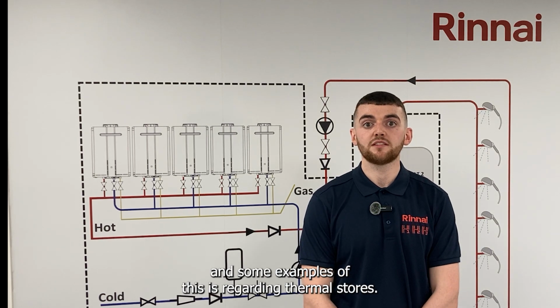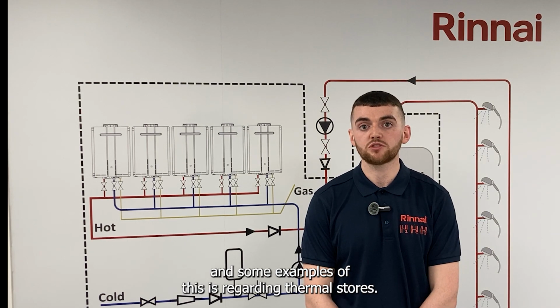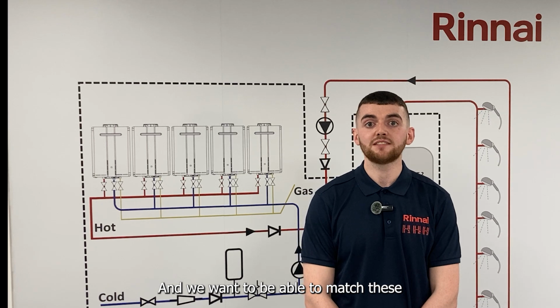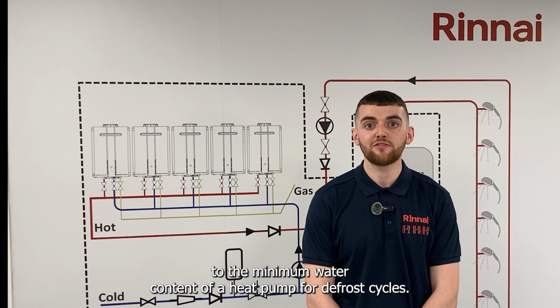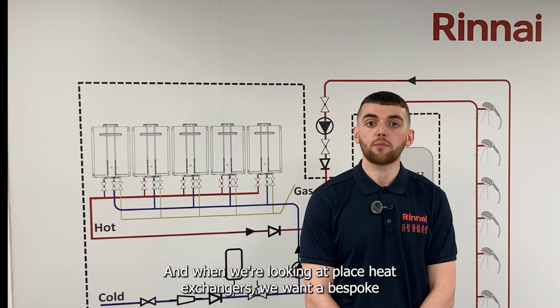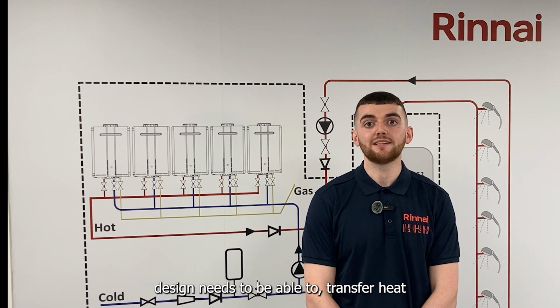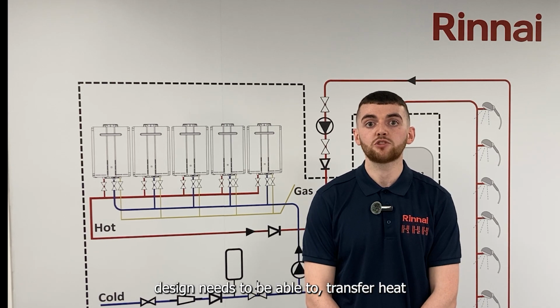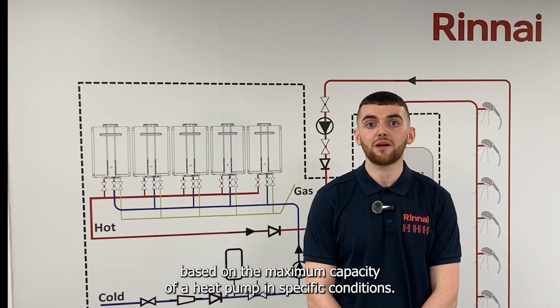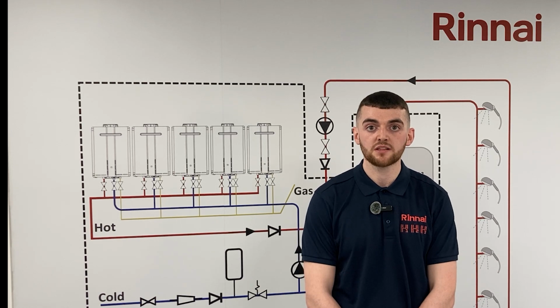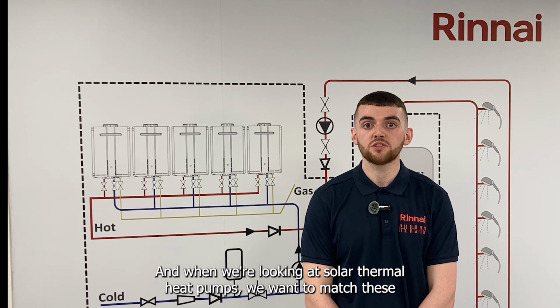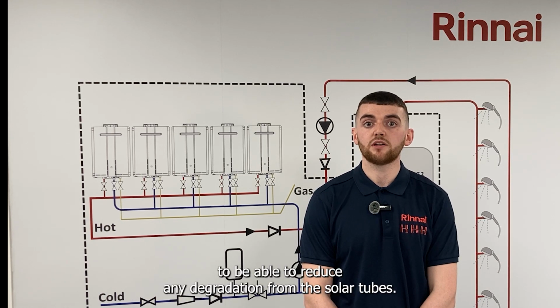Some examples of this are regarding thermal stores - we want to match these to the minimum water content of a heat pump for defrost cycles. When looking at plate heat exchangers, we want to bespokely design these to transfer heat based on the maximum capacity of a heat pump in specific conditions. And when looking at solar thermal heat dumps, we want to match these to reduce any degradation from the solar tubes.